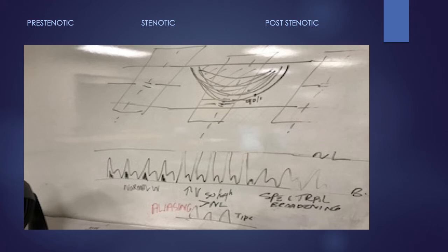There is no key for Nyquist limit, but this Nyquist limit equals PRF divided by 2. So if I want to increase the Nyquist limit, I can increase the PRF. But there is no key again to do that. So the key I use to increase the Nyquist limit or increase the PRF is increasing the scale. The key is scale. I can increase the scale. That will increase my Nyquist limit, and the tip will go back on. Okay.